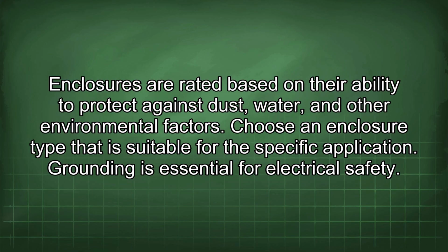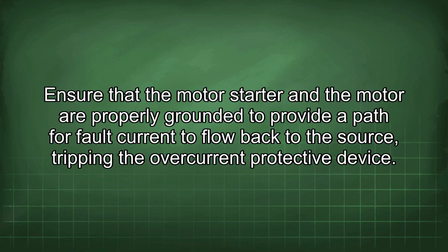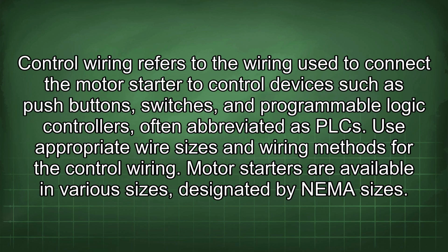Grounding is essential for electrical safety. Ensure that the motor starter and the motor are properly grounded to provide a path for fault current to flow back to the source, tripping the overcurrent protective device. Control wiring refers to the wiring used to connect the motor starter to control devices such as push-button switches and programmable logic controllers, often abbreviated as PLC. Use appropriate wire sizes and wiring methods for the control wiring.